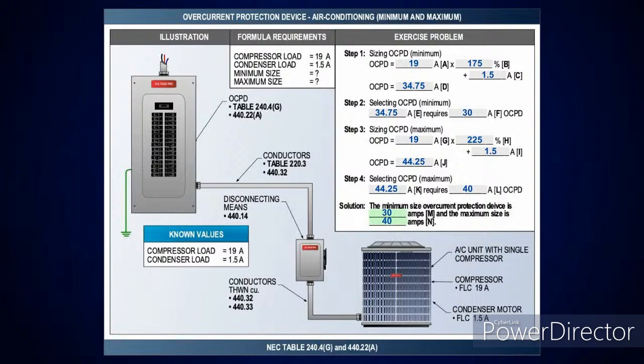Yeah, I did the calculation. It's 25.25 amps. If the condenser motor was 1 amp, then you could use a number 12. In this case, you'd need a number 10. Gotcha.